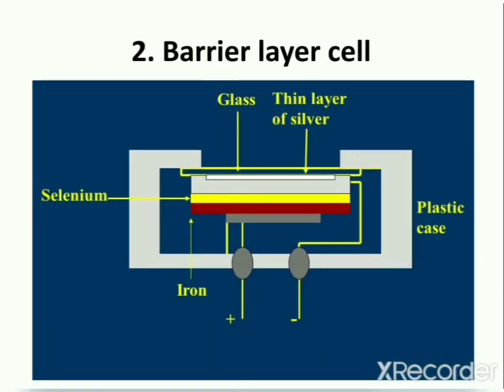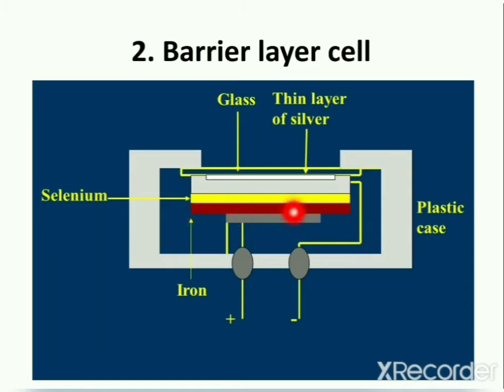The next main detector used in ultraviolet visible spectrophotometers is the barrier layer cell, also known as the photovoltaic cell. In its construction, it consists of a semiconductor selenium — the yellow portion denotes the selenium semiconductor. Selenium is deposited on a strong metal base such as iron — the red portion denotes the iron metal base. A very thin layer of silver or gold is deposited over the surface of the semiconductor, and this thin layer acts as a second collector electrode.